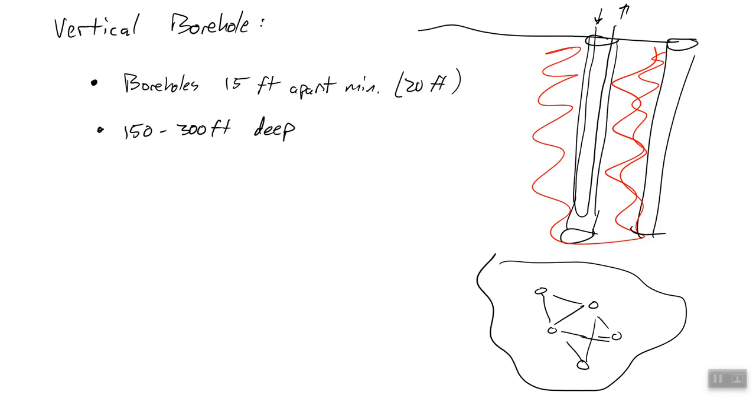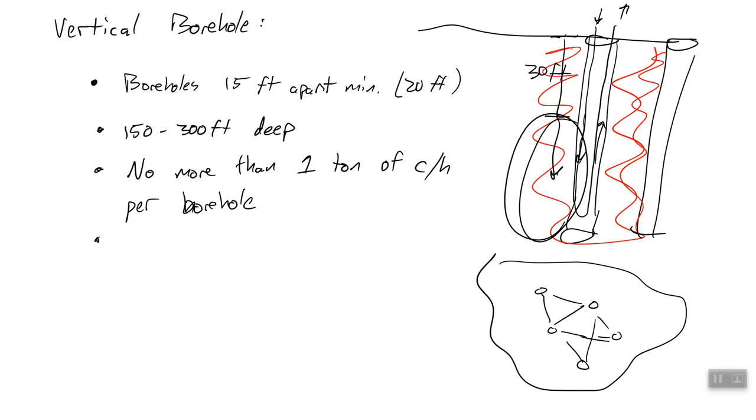As heat leaves a borehole, it's going to heat up the ground immediately around it, or cool the ground, depending on what mode you're in. If you have another borehole right next to it, that impacts the ability of that borehole to transfer heat as effectively. Your boreholes, you want to be 150 to 300 feet deep. About 30 feet into the ground, we see variation in temperature, but below 30 feet, the temperature is essentially the mean temperature of the air in your region. We also want no more than one ton of cooling or heating per borehole.